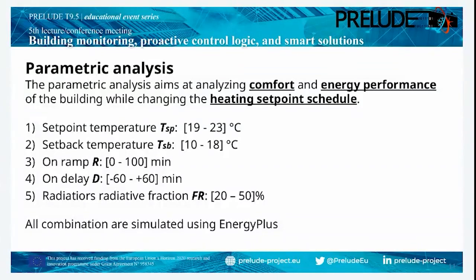So what we changed was the set point temperature from 19 to 23 degrees, the setback temperature — the temperature when the system is basically off — a ramp parameter, which is the time slot used to change from the setback to the set point, and then a delay, basically shifting the schedule later or earlier.